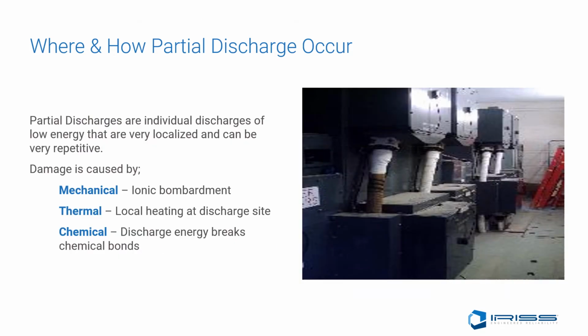So what are the effects of PD? Partial discharges are individual discharges of low energy that are very localized and can be very repetitive. The damage is caused either through mechanical, which is ionic bombardment, thermal, which is the local heating at the discharge site, or chemical, which is discharge energy breaking down chemical bonds.